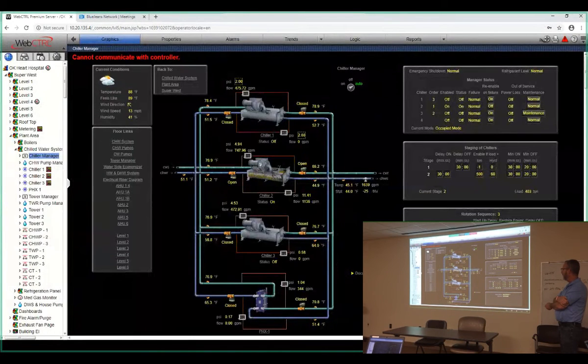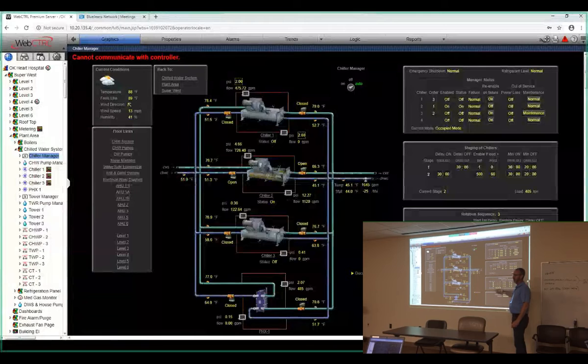So we just rotate through these 3 different rotations. So whenever we change next time, we'll roll over. Chiller 1 will be the lead. Chiller 2 would be the lag. Chiller 3 would be the redundant. We'll rotate again. Now chiller 3 is the lead. 1 is the lag. 2 is the redundant. Does that make sense how it's rotating? These are not the chiller numbers. These are the order of sequence that they run.